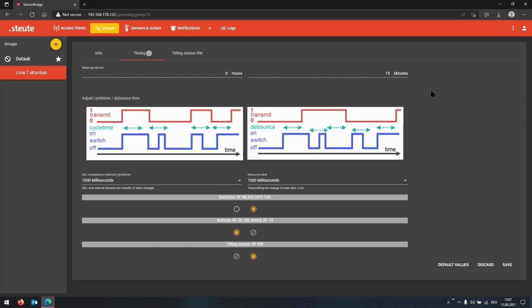to say that the sensor is still there, together with its switching status and all further functions. If a sensor is actuated every minute, then it will never send a wake-up notification because the notification is always sent 15 minutes after the last actuation. In contrast, if a sensor is never normally actuated, it will send a wake-up notification every 15 minutes.